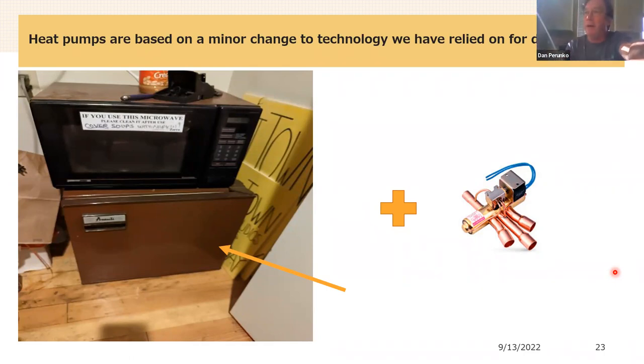And what makes all of that possible is this valve right here. This valve simply changes the direction of flow of refrigerant inside the what would have been an air conditioner. So inside the heat pump, outside. And so heat pumps are typically an inside unit and an outside unit. So within the outside portion, we've added this four-way valve, and it simply just changes the direction of refrigerant flow, which flip-flops the functions. Now we're absorbing heat from the outside and releasing it on the inside, and that's what a heat pump does as opposed to an air conditioner, right?